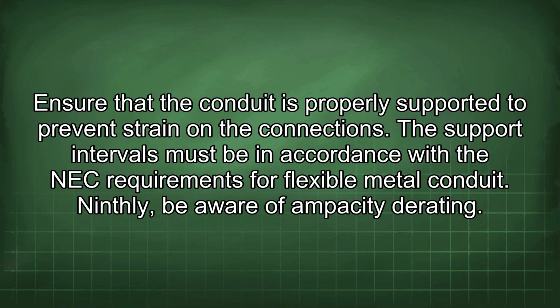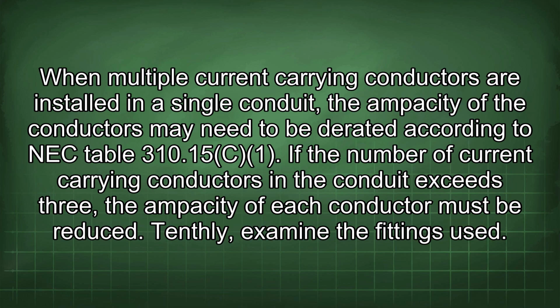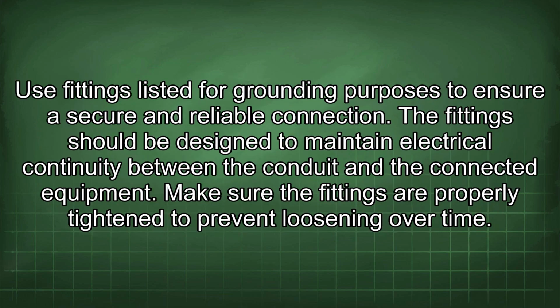Ninthly, be aware of ampacity derating. When multiple current-carrying conductors are installed in a single conduit, the ampacity of the conductors may need to be derated according to NEC Table 310.15(C). If the number of current-carrying conductors in the conduit exceeds 3, the ampacity of each conductor must be reduced. Tenthly, examine the fittings used. Use fittings listed for grounding purposes to ensure a secure and reliable connection. The fittings should be designed to maintain electrical continuity between the conduit and the connected equipment.